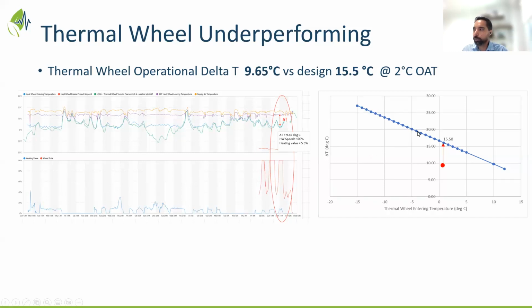However, as your entering air to the wheel decreases, as you see coming down the slope, your delta T across the wheel also decreases, which is limiting the capacity of your thermal wheel. In this particular example, the delta T at 2 degrees C was expected to be around 15.5, whereas the wheel was only delivering 9.65 degrees C. So from this analysis, you could suggest that the wheel is definitely not performing to the design condition, because at the design condition, if the entering air to the wheel is 2 degrees C, then your delta T coming out of the wheel should be 15 degrees C. However, the delta T we're seeing through the trend analysis was 9.65. So this points to the next step: there is definitely an operational issue, or the wheels are underperforming.